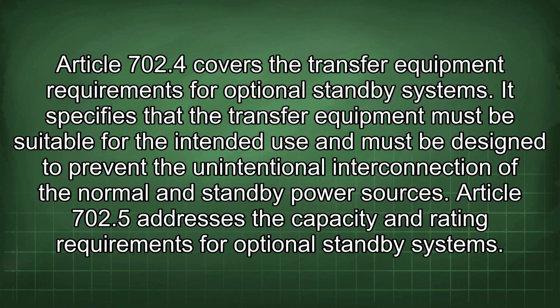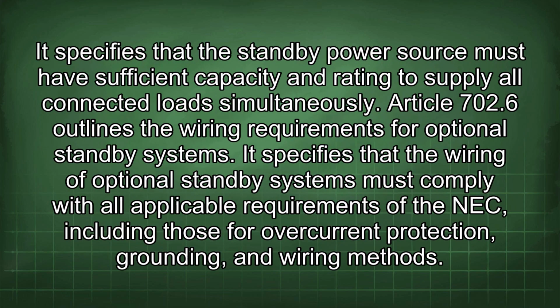It specifies that the transfer equipment must be suitable for the intended use and must be designed to prevent the unintentional interconnection of the normal and standby power sources. Article 702.5 addresses the capacity and rating requirements for optional standby systems. It specifies that the standby power source must have sufficient capacity and rating to supply all connected loads simultaneously. Article 702.6 outlines the wiring requirements for optional standby systems. It specifies that the wiring of optional standby systems must comply with all applicable requirements of the NEC, including those for overcurrent protection, grounding, and wiring methods.